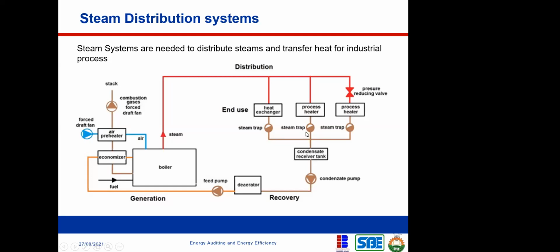So this is another process. You have several steam traps across the processes. At every point, you know that the steam is going to condense and form water, so you put a steam trap to remove the water. Otherwise, it's going to cause a problem. That's what we call water hammering. It will make noise in the pipe as the steam flows along the pipe. It's going to make undue noise, and it can also create damage.